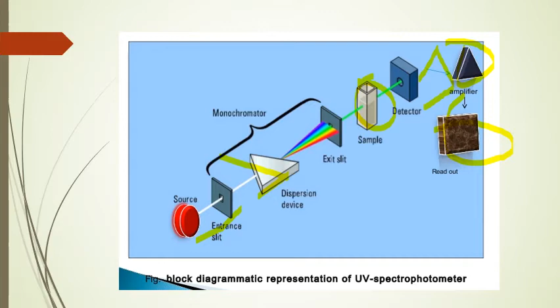Monochromator consists of three parts. One is the entrance slit, we have the dispersion device which converts the polychromatic radiation into monochromatic radiation, and the exit slit to pass the monochromatic radiation. Then we have the sample, which is detected by the detector which converts it into a signal, and we have the amplifier to amplify the signals, and finally it is recorded in the recording unit. So here you can easily see the role of the monochromator, with the entrance slit, dispersion device, and the exit slit.